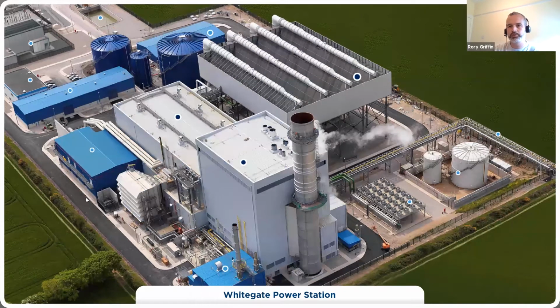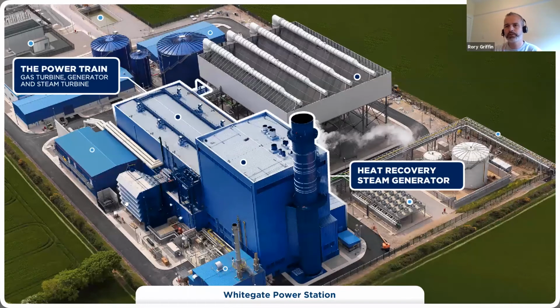So air will be sucked in through the filter house here. There's 2 stages of filters. The filters out at the front really is to stop coarse material such as leaves, airborne debris from entering the machine. And then as you get into the next phase, they're quite fine. It'll block pollen, airborne pollution. It's a maritime environment, so salt, etc. will be blocked. So a bit like the requirement for the gas fuel to be heated up and also the water to be of a very clean quality, we need the air as clean as it can be as well going into the machine.